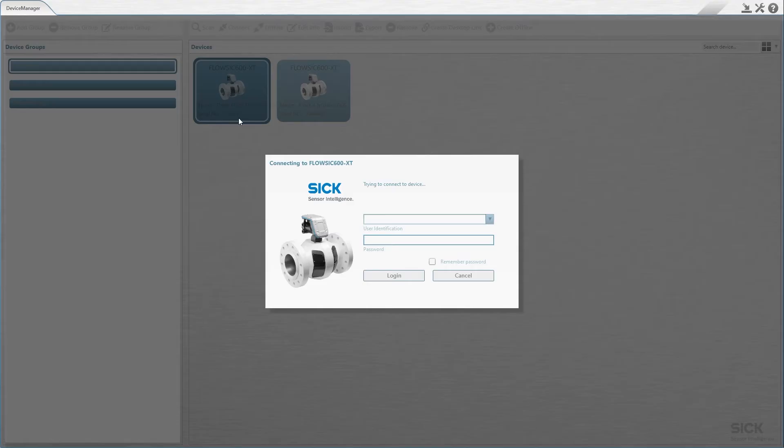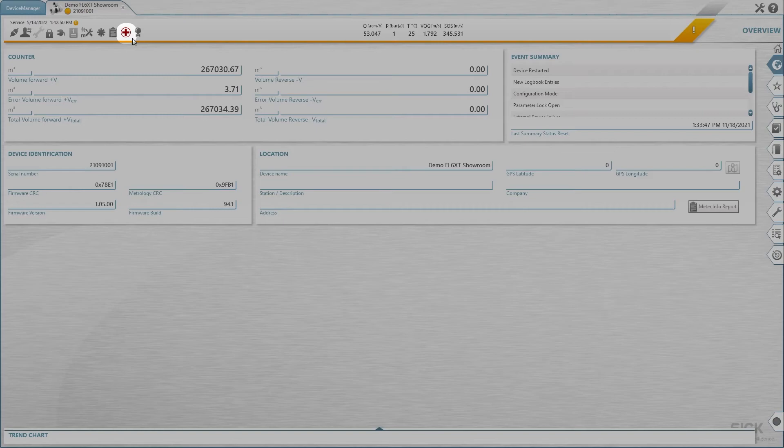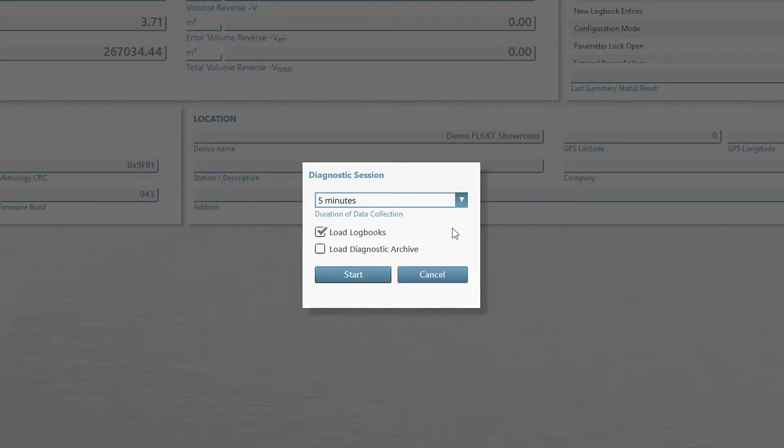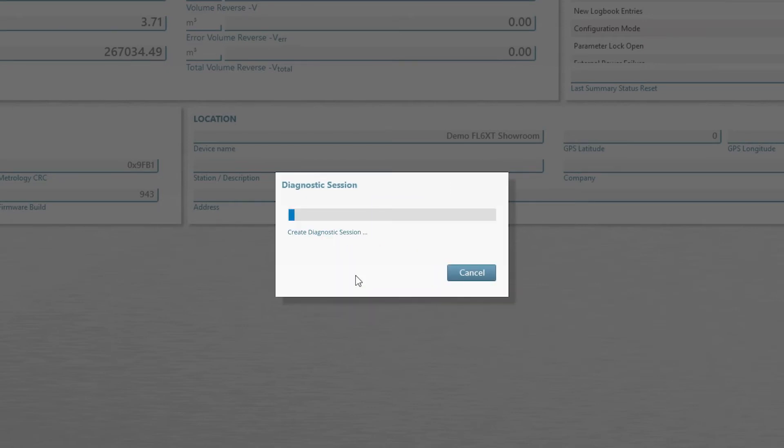To create a diagnostic session, first connect to the meter. Next, click on the Diagnostics icon in the status bar. You must select the recording time, and you have the option to select logbooks and archives to be added to the session file. A recording time of 5 minutes is generally recommended. Next, click on Start.